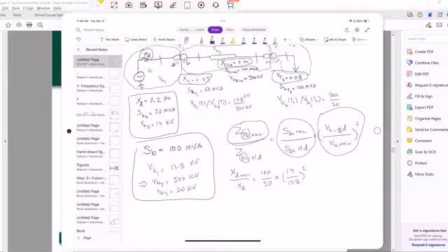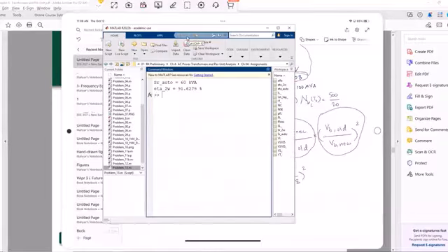Now, we have to put V base old. So what is V base old here in the nameplate? 14. And V base new is obviously V base 1. We have to choose the V base which is on the side of that device, which would be V base 1 in this case. So this gives us whatever value. XD was 0.2. If I do it in MATLAB, this will give me 2 times (14 over 13.8) squared times 0.2.